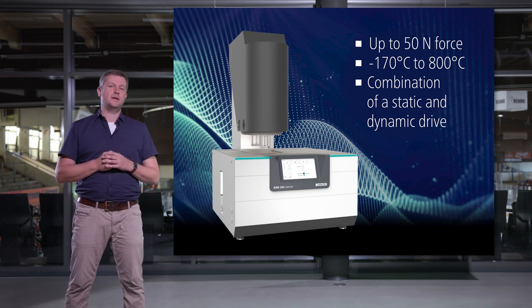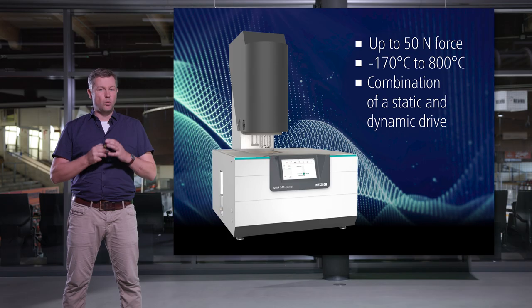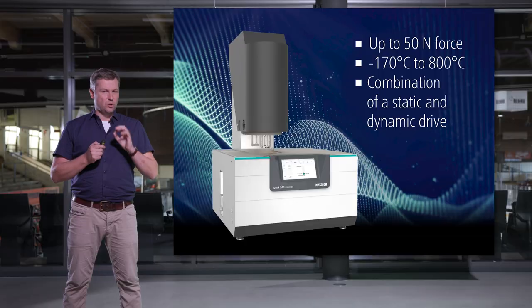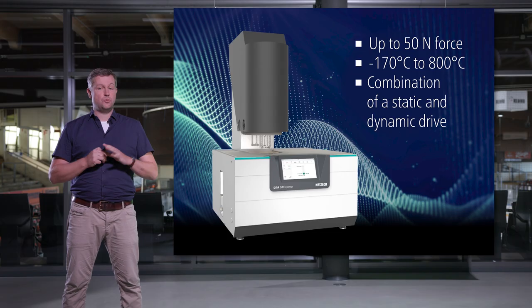These features make the DMA 303 a unique desktop DMA. With forces up to 50 N, you can measure many samples even in tensile mode. The wide temperature range from minus 170 to 800 degrees opens new applications. The combination of a static and a dynamic drive provides great flexibility — whether you are interested in complex modulus, creep and relaxation, or even universal testing of smaller samples, the DMA 303 Eplexor can do it.